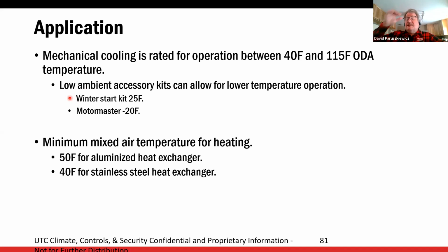The winter start kit does this: when you start an air conditioner in the middle of winter, until you build head pressure, our suction pressure is going to be really low because we don't have a pressure drop across our metering device. So we're not flowing through there, and suction pressure is low. The winter start kit is basically a time delay that bypasses the low pressure switch for 3 minutes to allow the head pressure to build up, because the head pressure starts the pressure drop into the low side. We start to flow refrigerant and our suction pressure comes up. The winter start kit is good down to 25. The Motor Master's good down to minus 20, but we also need the winter start kit. So if you're doing low ambient on rooftop units with Motor Masters, you have to use the winter start kit or you're going to short cycle.